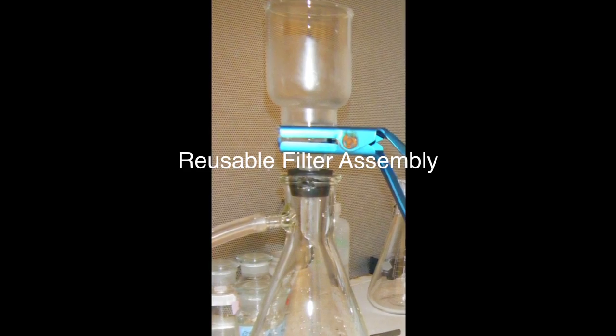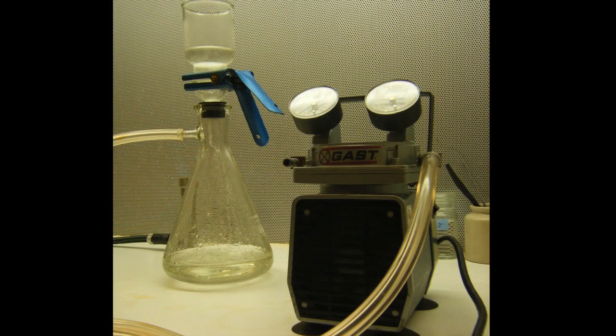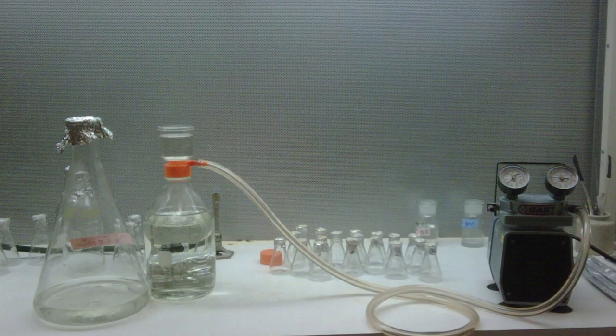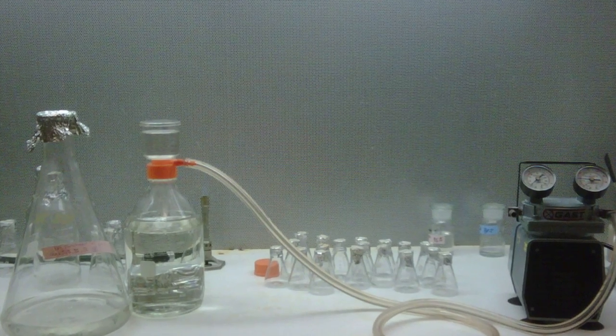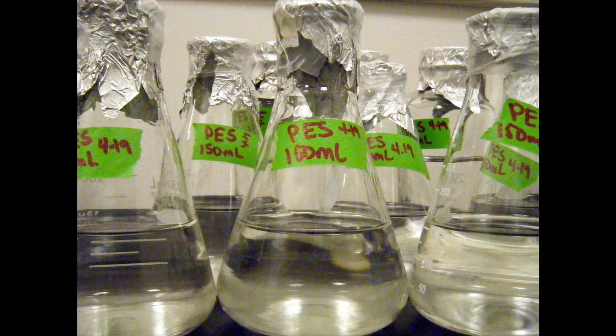Enclosed, high-energy UV bulbs can be installed as part of the water filtration process. Filter sterilization uses very fine filtration to exclude all living organisms, effectively sterilizing water without the application of heat. For small volumes, a reusable or disposable filter assembly is set up on a side arm flask and liquid is pulled through the filter using a vacuum pump.